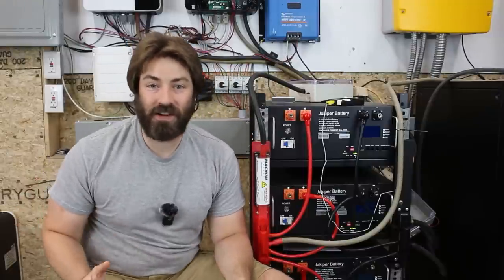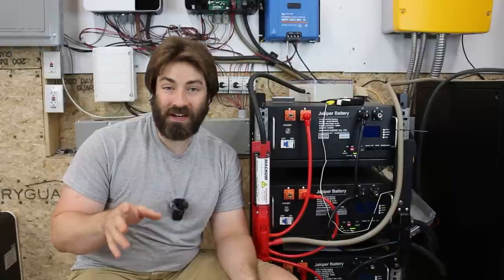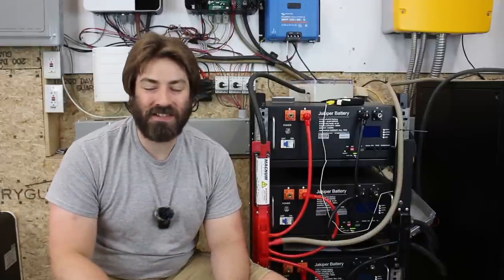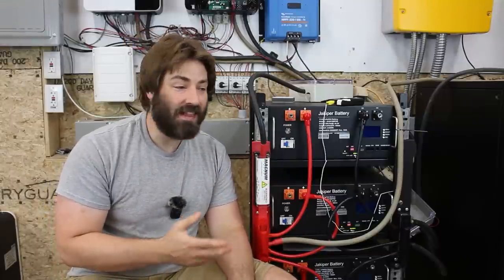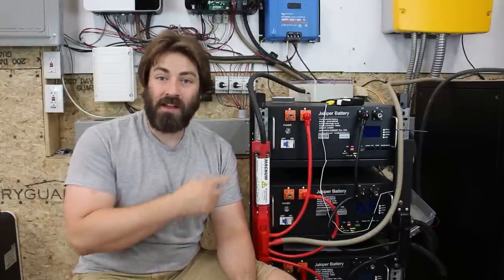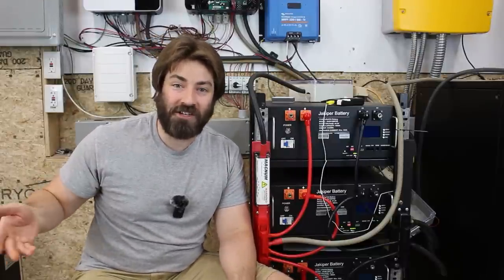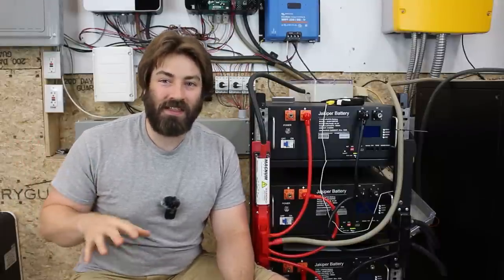That is a massive reduction — 29 degrees Celsius cooler than before. Remember, all heat loss out of a system is energy loss. And because it's the middle of summer, the heat loss into this environment means I have to run additional energy for the air conditioner to remove that heat from this environment.